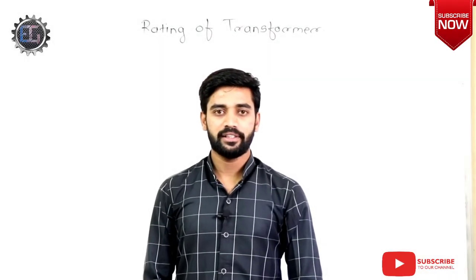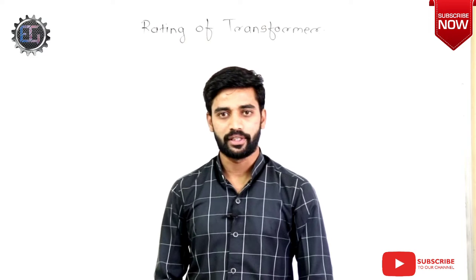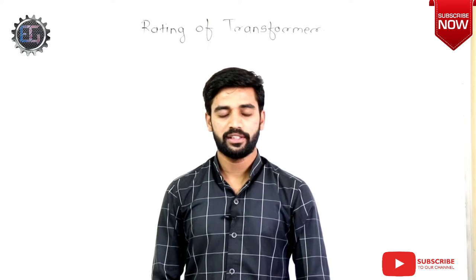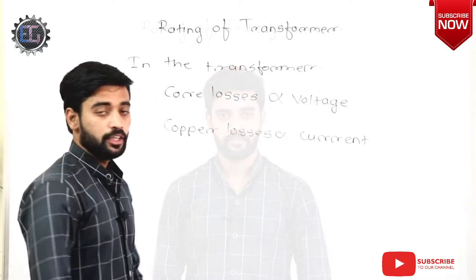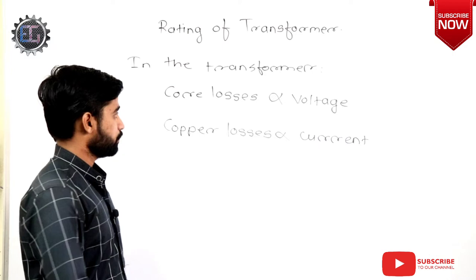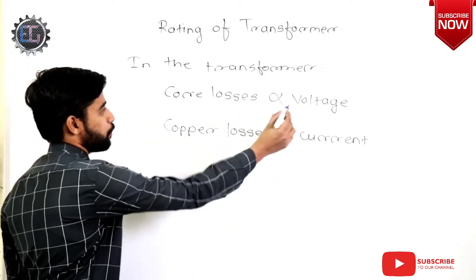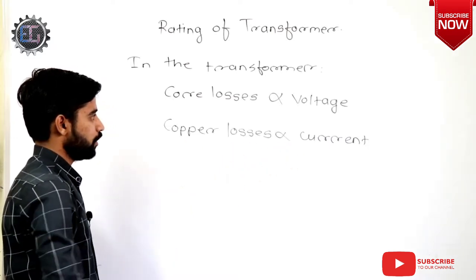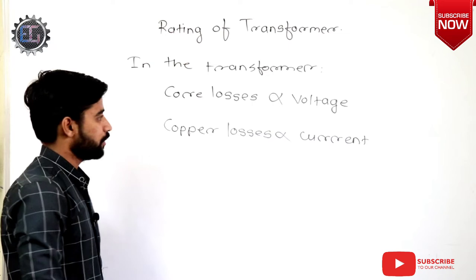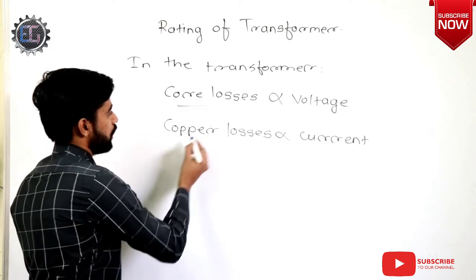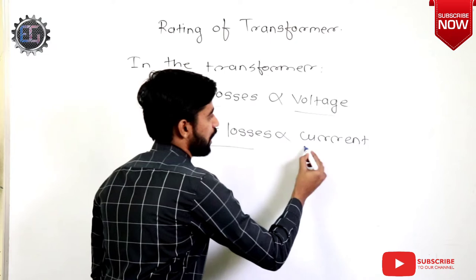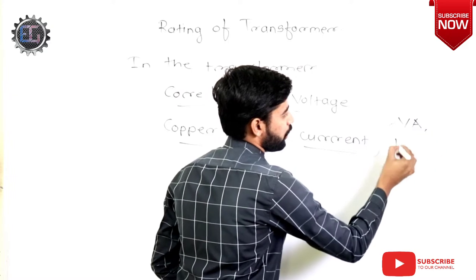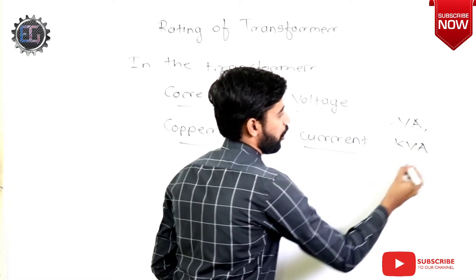Why are all other electrical appliances specified in terms of watts or kilowatts, but the transformer is specified in terms of KVA? The normal answer people use for this question is: in the transformer, core losses are proportional to voltage and copper losses are proportional to current. All losses responsible for temperature rise — core losses and copper losses — are due to voltage and current. Hence the transformer is specified in terms of VA, KVA, or MVA.